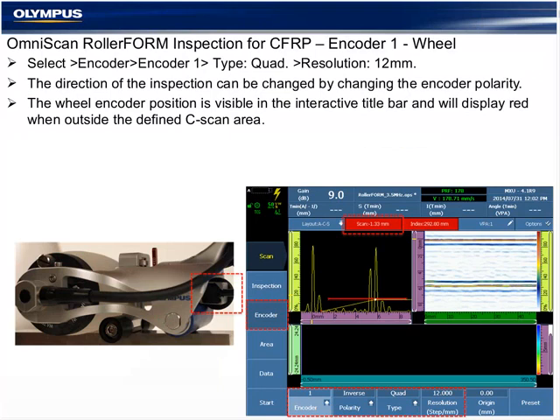This encoder 1 is slaved to the scan axis, which is also always visible in the interactive title bar. When this number is red, it means that the current encoder position is outside the defined area of the C-scan. When it's blue, it means it's inside.